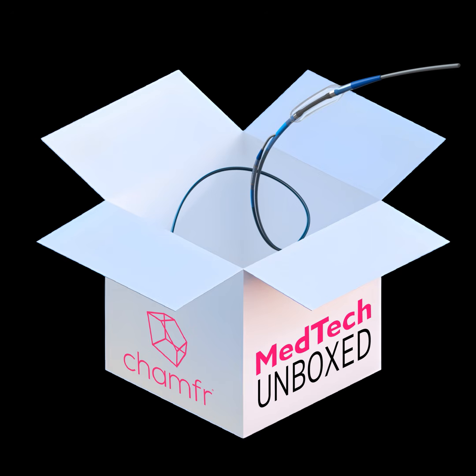Sure. So when you look at the chemical structure, PTFE is the most inert and most lubricious polymer in the world, hands down. There's nothing that can beat PTFE in terms of its coefficient of friction in its natural state, whether in dry or wet condition. So it's been used in our industry for over 30 years. Almost every delivery system and catheter that you see out there uses PTFE. And there's a reason behind that.